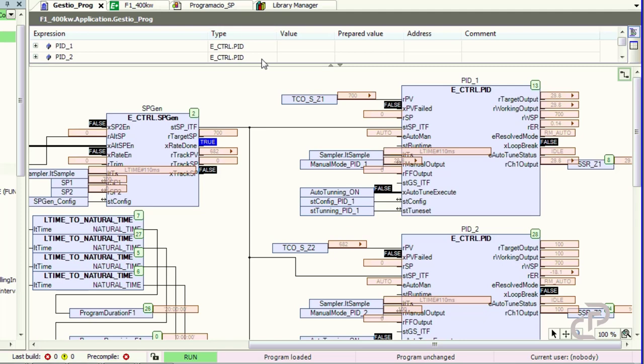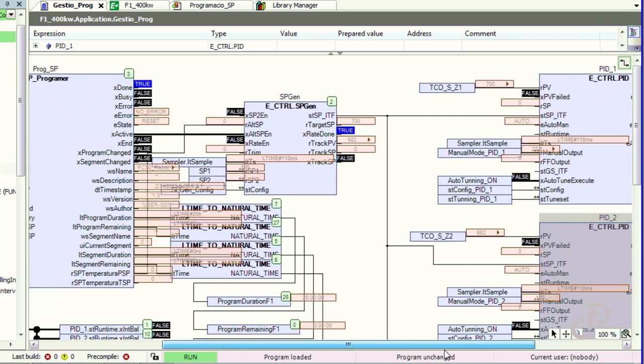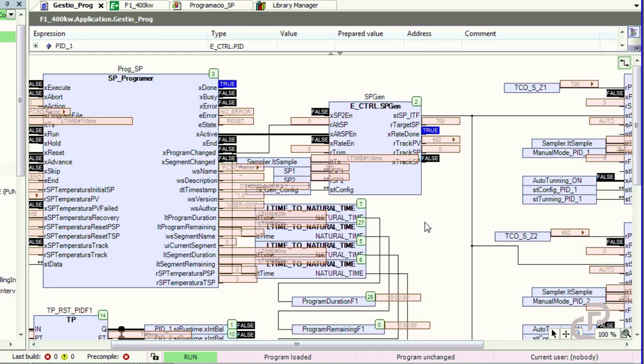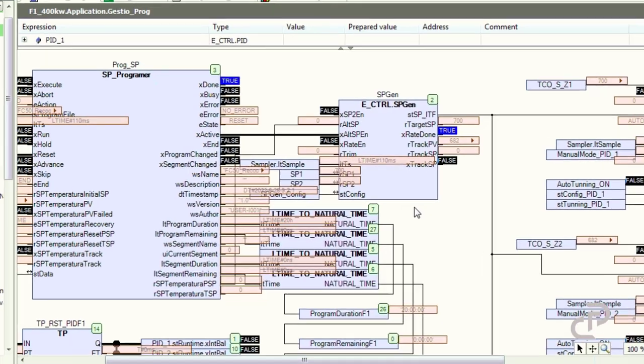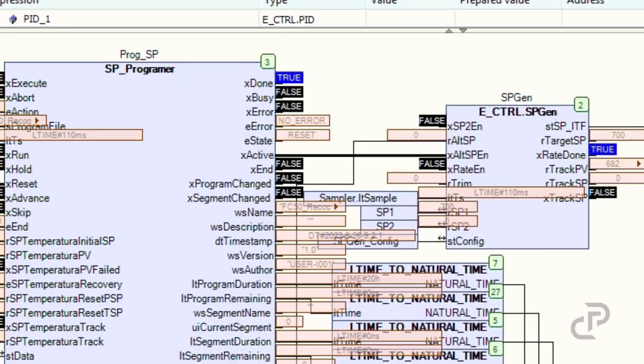Here I will show you the online mode. The setpoint is 700 and the PID function output is now 27 percent. In another video I explained how to give this value to the digital output module. In the setpoint generator, x_alt_sp_enable is currently false, so it takes the setpoint from SP1 which equals 700. As soon as x_alt_sp_enable is true, the setpoint becomes equal to the output of the setpoint programmer.